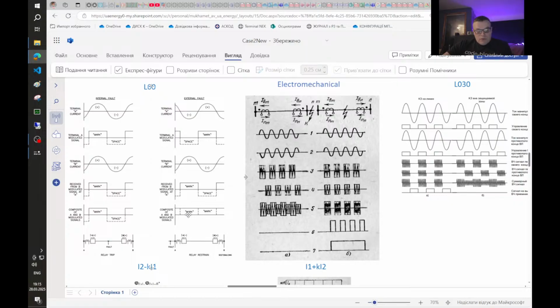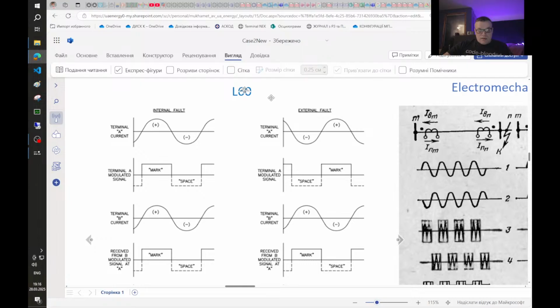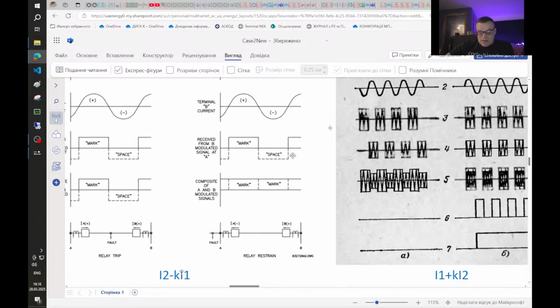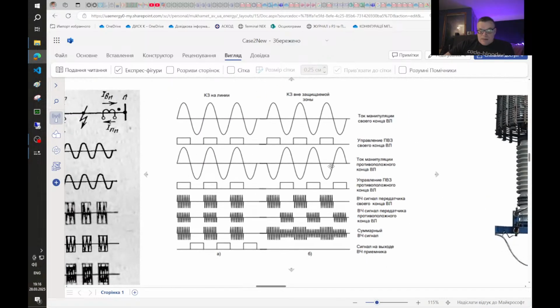But on an external fault in a high frequency communication channel, there will be a high frequency signal without interruptions. And if you look at the picture from the L60, there is also a signal without pauses. And here also for an external fault, we can see that in this case, in the high frequency communication channel, there will be a high frequency signal without any pauses.